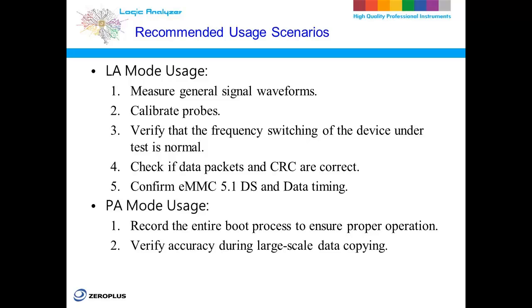Calibrating probes. When setting up your measurement system, ensuring that probes accurately capture the signal is crucial. LA mode can help you check if the probes are reflecting the signal changes correctly, allowing you to make necessary adjustments to ensure measurement accuracy. By using LA mode, you can review the signal output from each probe, fine-tune them, and make sure they are capturing the signal accurately. Ensuring the probes are calibrated in LA mode helps prevent misinterpretation in PA mode.